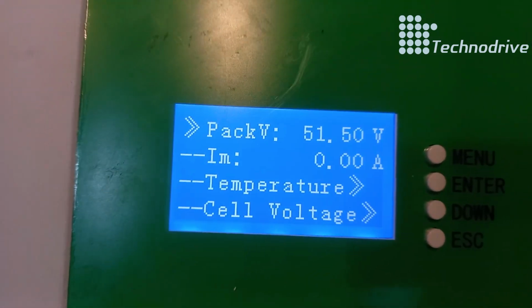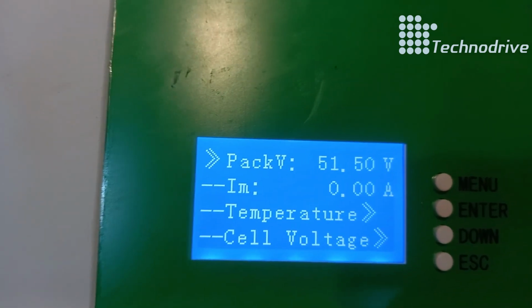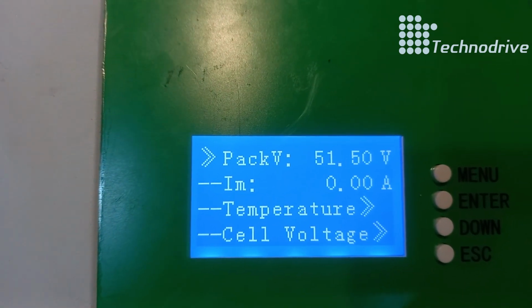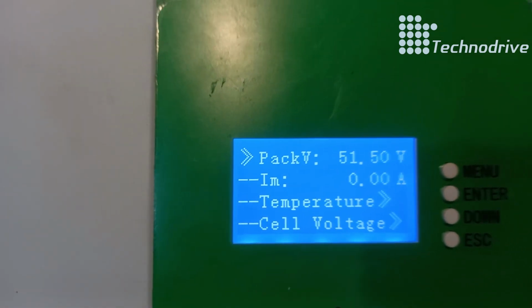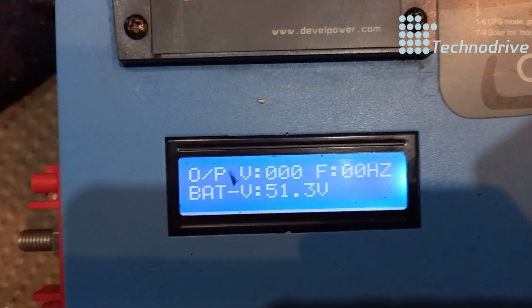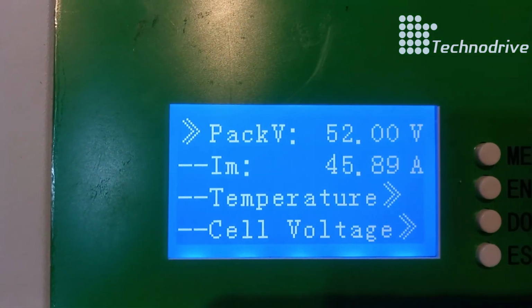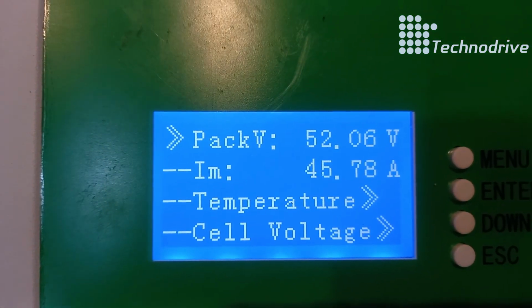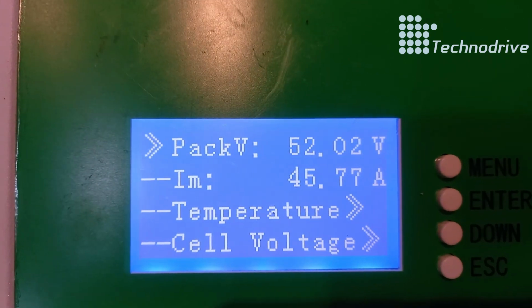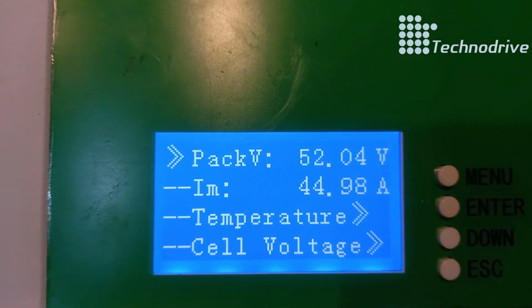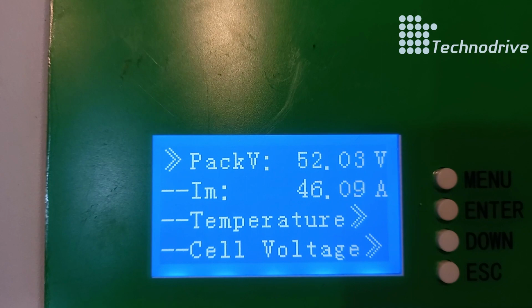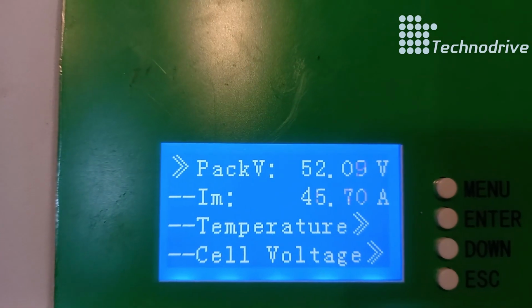Let me switch on the inverter, take a look at the current. The inverter is on there. You can see the battery voltage is 51 volts. Now the incoming current is 45 amps, so this inverter is now on charge mode, charging with 45 amps.